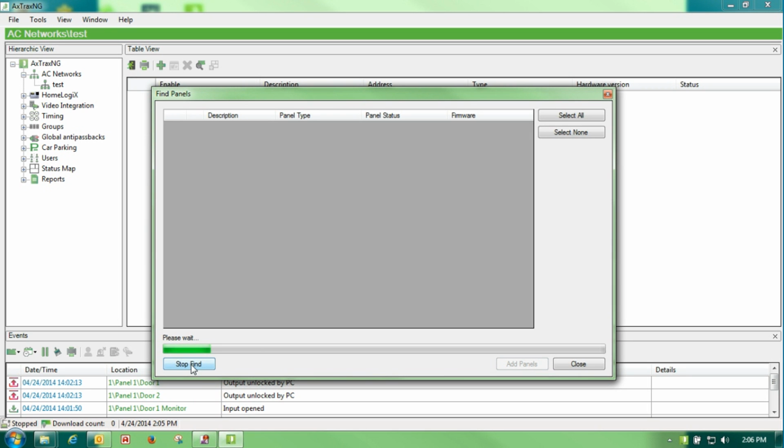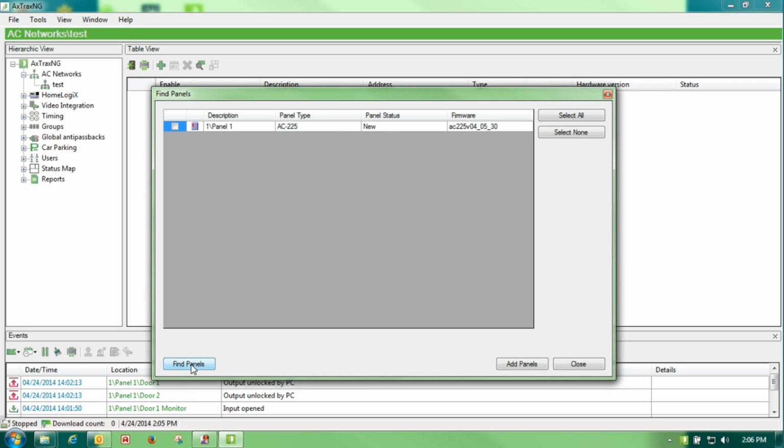One way that you can always do a verification on your panel, whether your software is talking to it and requesting, is if you look at the bottom right hand side of your panel, you'll see a red and green transmit receive light. The green receive should be blinking about once every 7 seconds if the software is getting to the panel and doing its request. You'll see that flash.